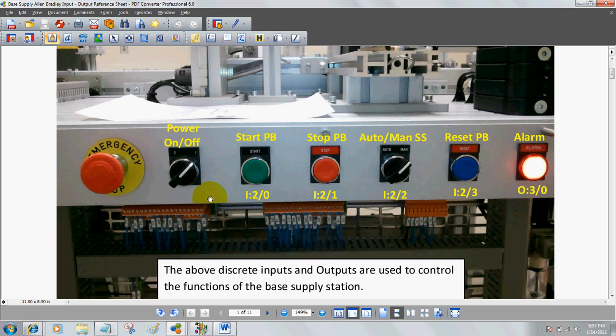Let's take a look at the actual operator panel. We've got the emergency stop, which will kill all power to the PLC, and the power on-off switch, which also kills all power to the PLC. We've got some discrete inputs: the start PB, which is I:20; stop PB, which is I:21; and the auto/manual selector switch. Note this is a maintained position switch — when you turn it one way it stays in that position — and it only has one address, I:22.